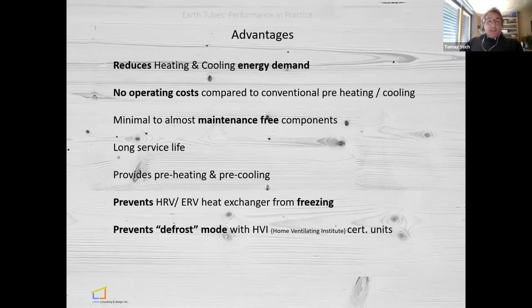So the HRV units that are used in passive houses are passive house certified. So it's different than Home Ventilation Institute. They don't have a defrost mode. This is why an earth tube is really handy, because the electrical preheater in the HRV or ERV doesn't turn on at all.